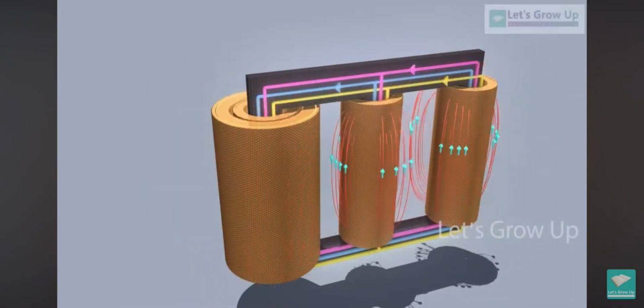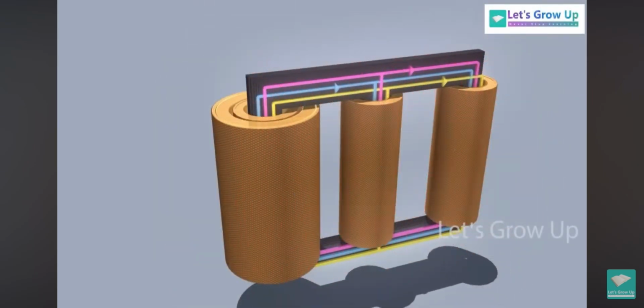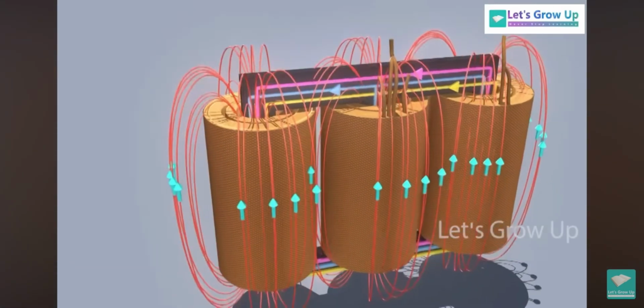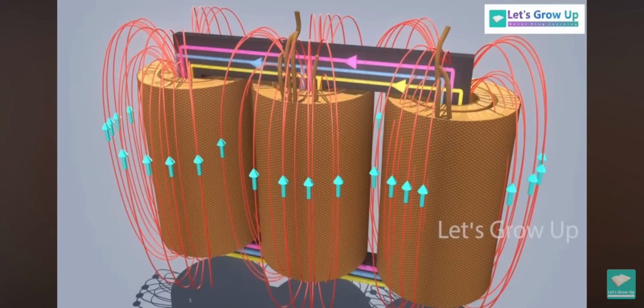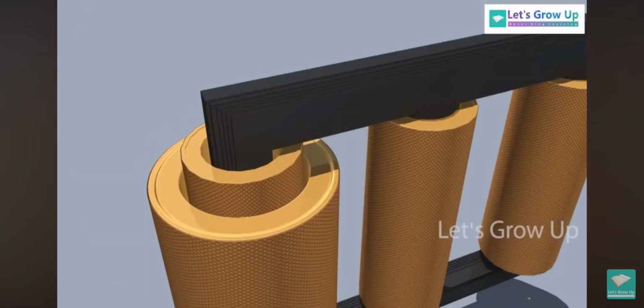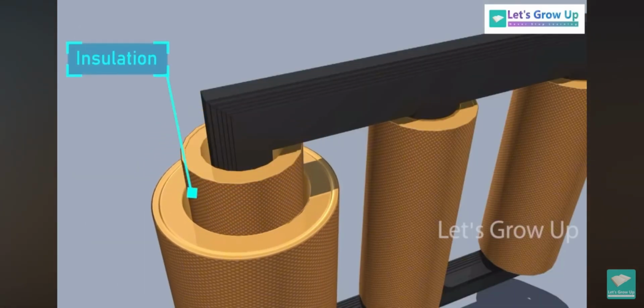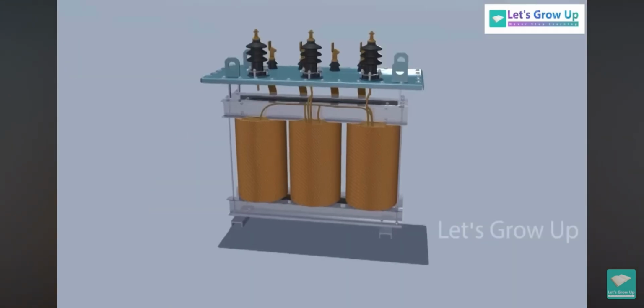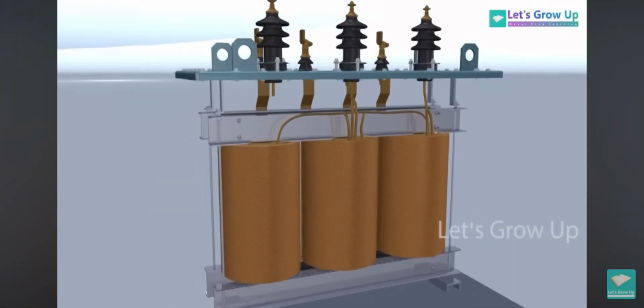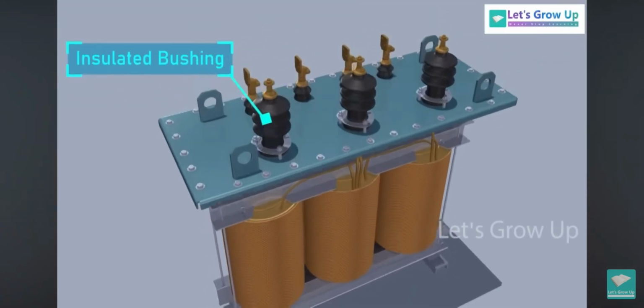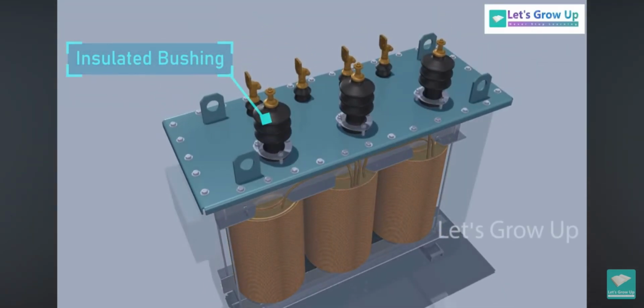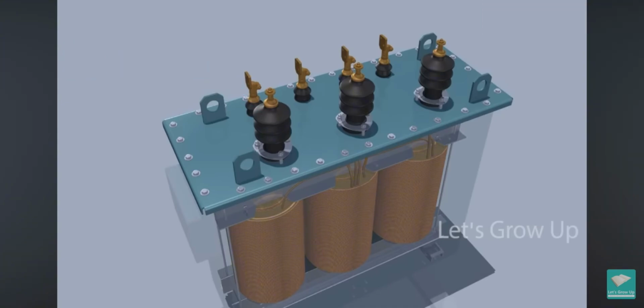The alternating current through the primary winding of each phase produces a continually changing magnetic field that surrounds the winding. Here, this magnetic field is linked with the secondary winding by magnetic flux which flows through the transformer core. EMF will be produced at the secondary winding based on Faraday's law, and this induced EMF is defined as mutually induced EMF. Insulation is needed between primary and secondary windings to prevent short circuit. To receive electric energy from the transformer, insulated bushings are needed.